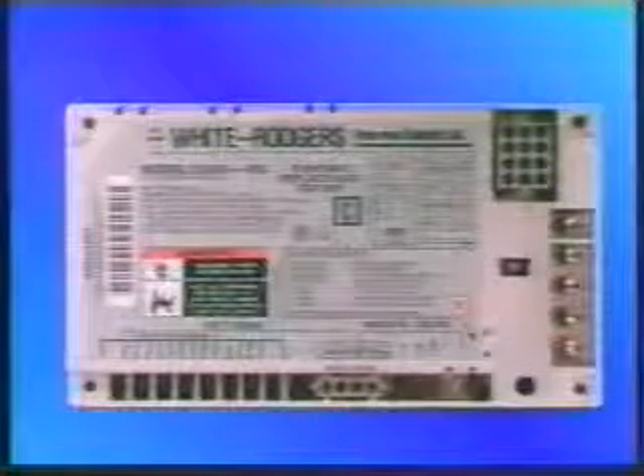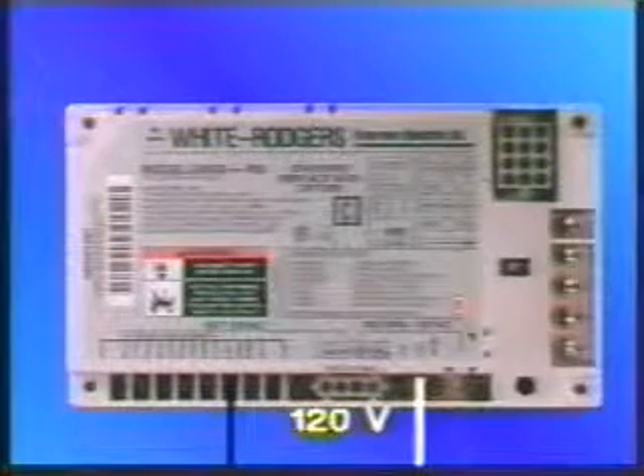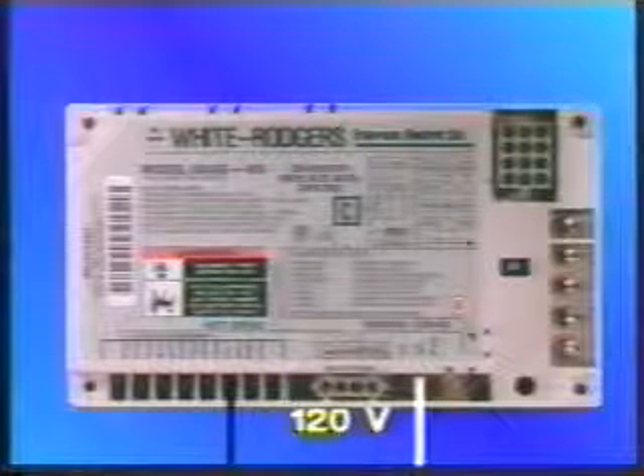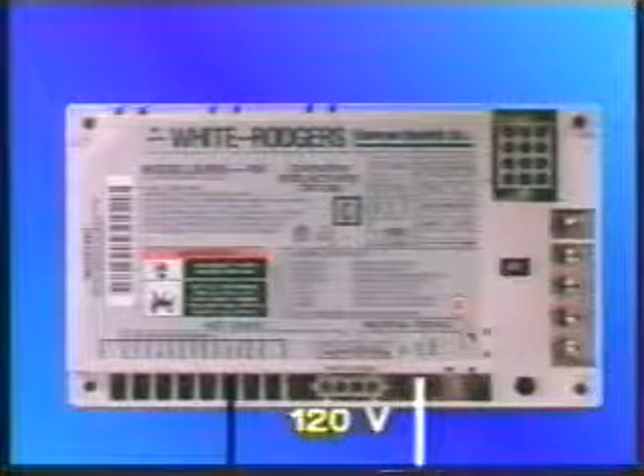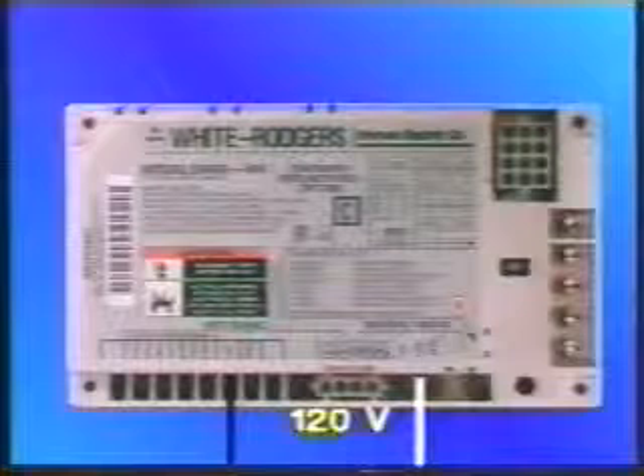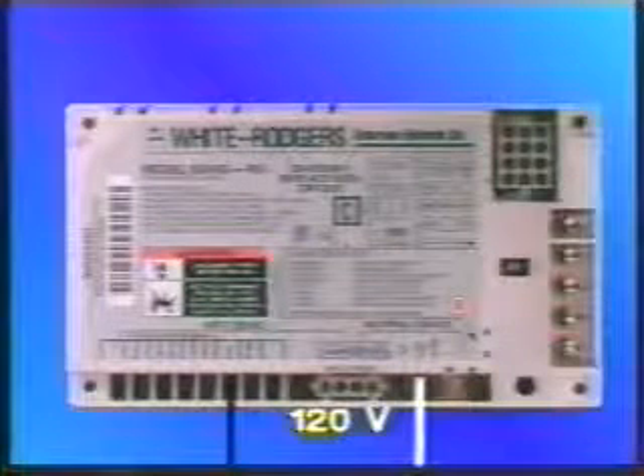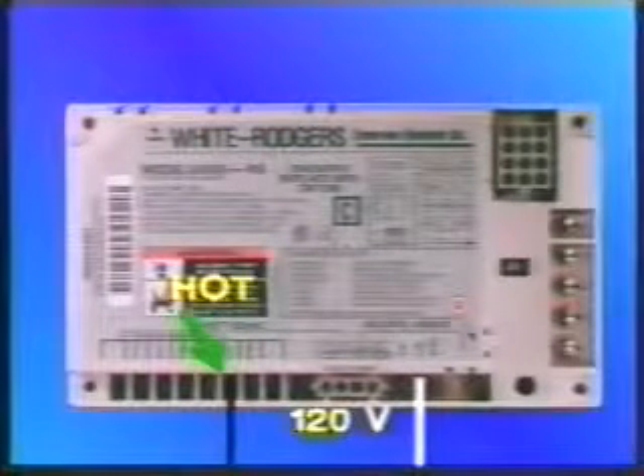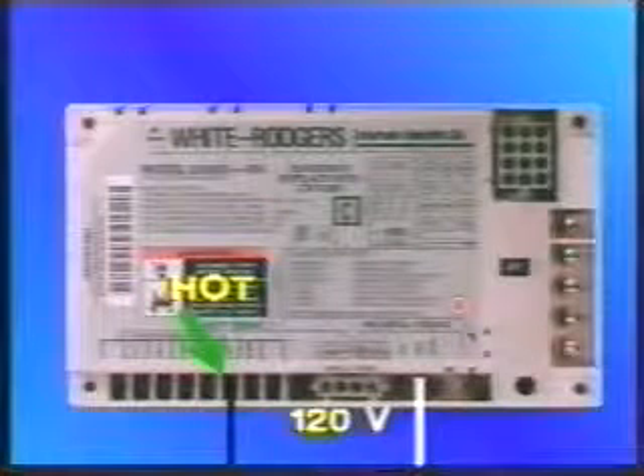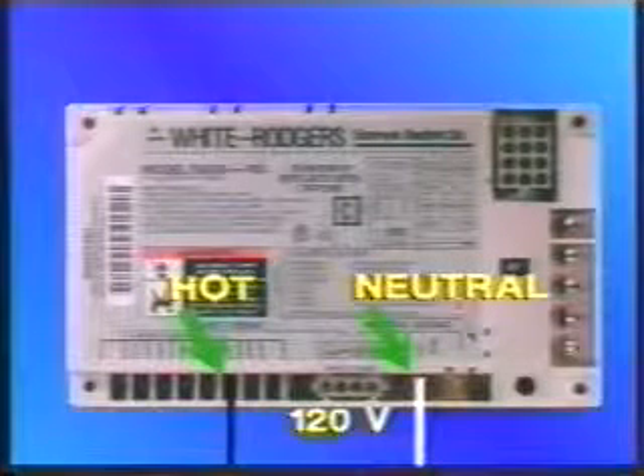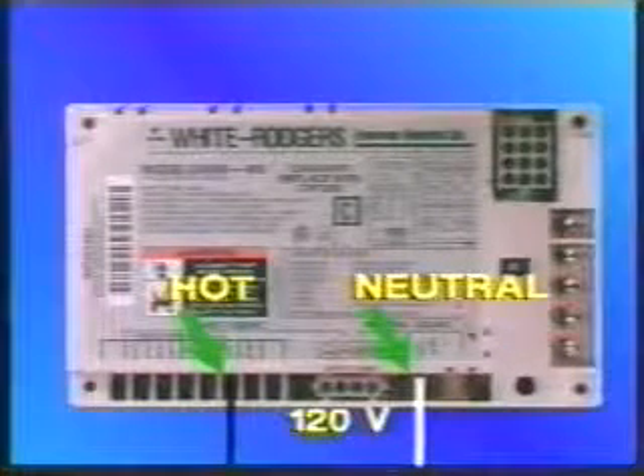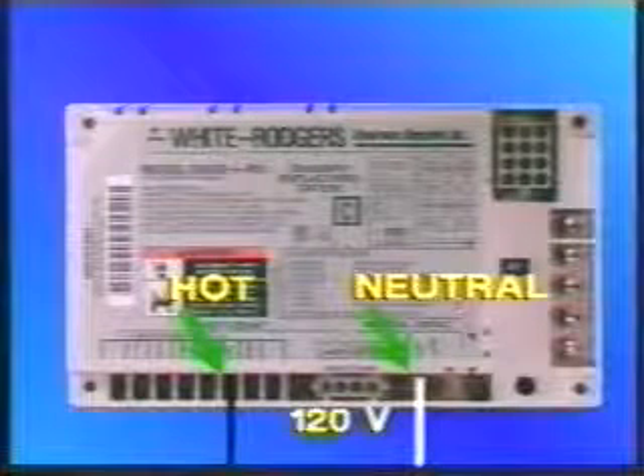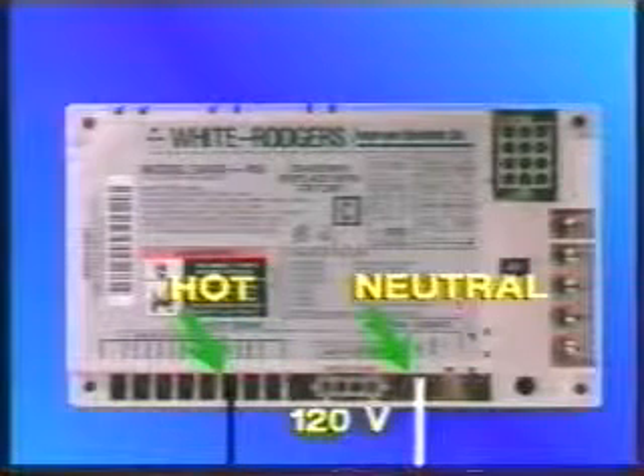The source of all power for the module is a 120-volt direct connection from the furnace electrical junction box. This wiring must be made with proper polarity and ground connection. The hot side of the line must be connected to the hot terminal, and the neutral must be connected to the neutral terminal. If the 120-volt wiring is reversed, the module will lock out.